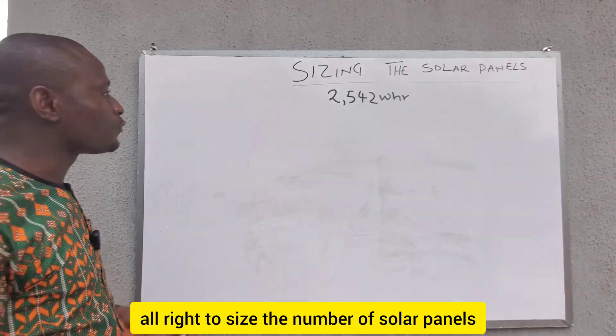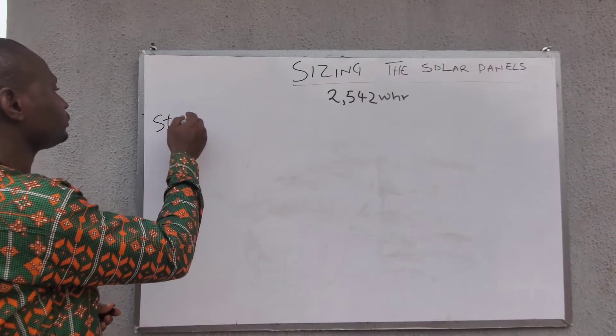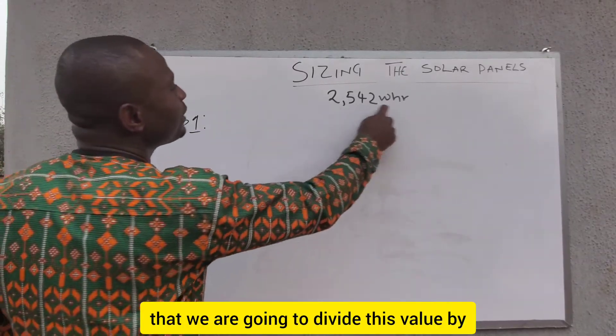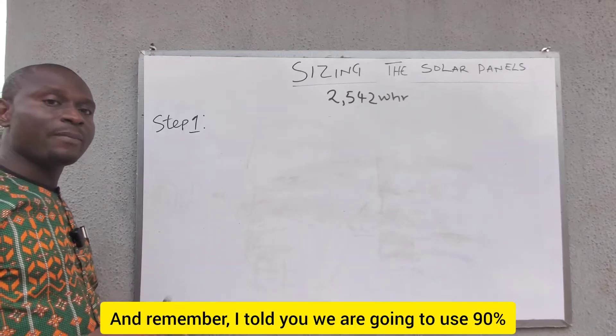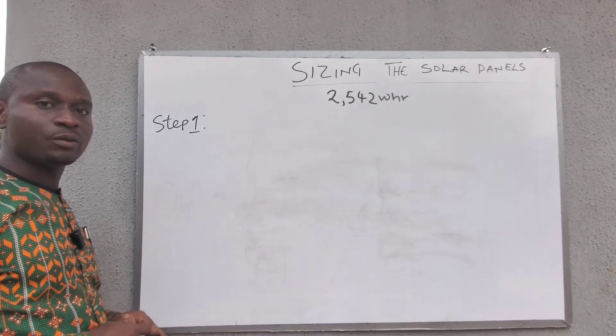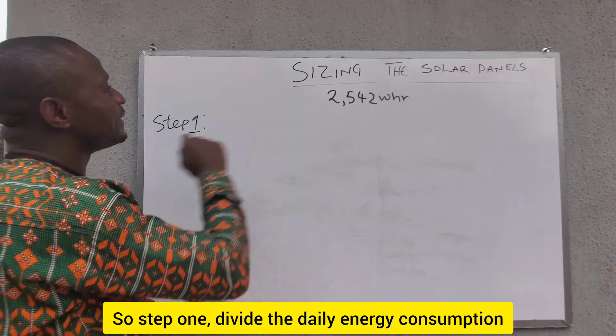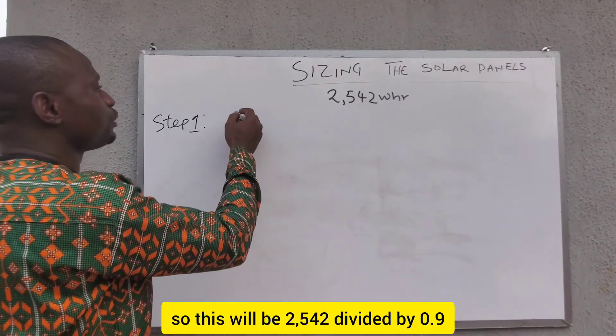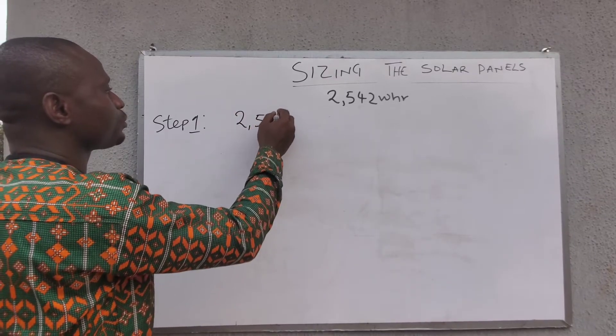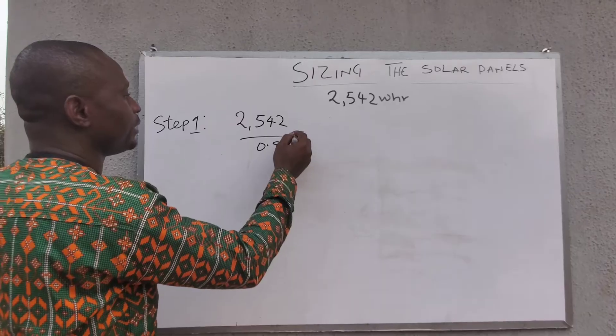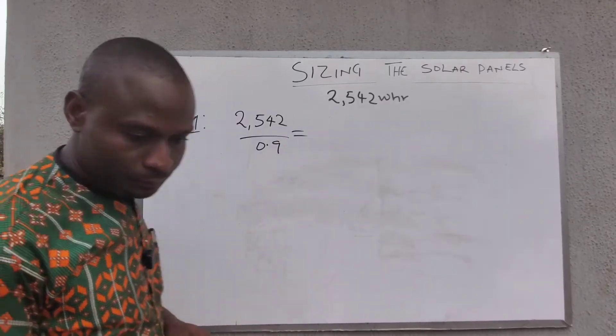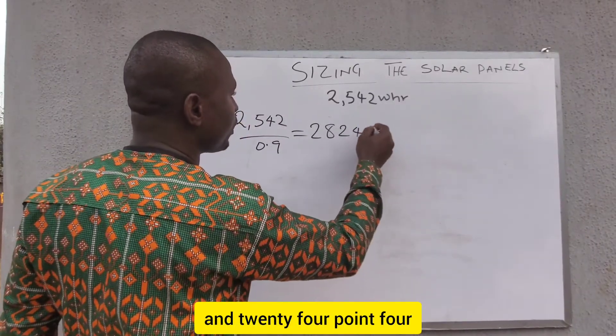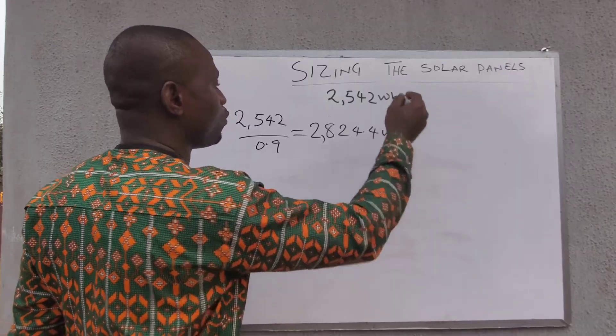Now I'm going to show you how to size the solar panels using our daily energy consumption of 2,542 Wh. Step 1: divide the daily energy consumption by the inverter efficiency. So 2,542 divided by 0.9 gives us 2,824.4 Wh.